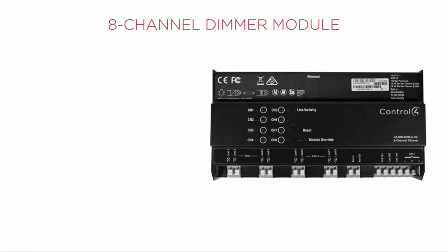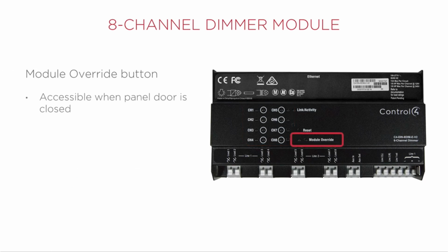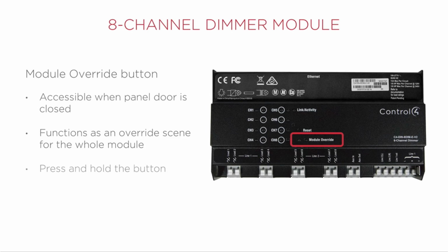The dimmer module includes an override button, which is also accessible when the panel door is closed. This button functions as an override scene for the whole module. After the loads have been individually set to their desired levels, press and hold the override button to save a module scene. The button can be pressed to toggle that module scene.